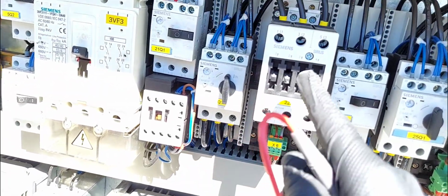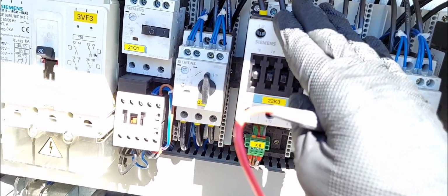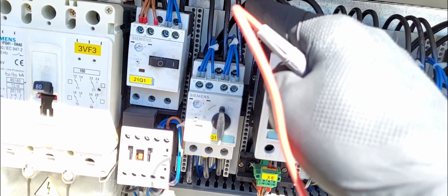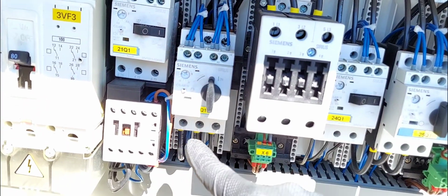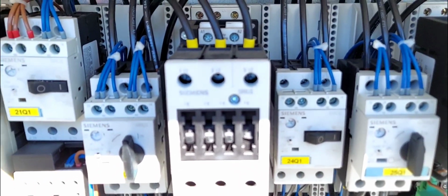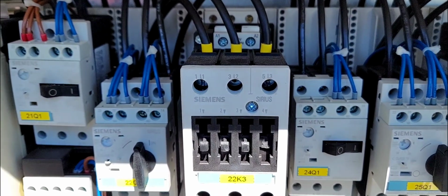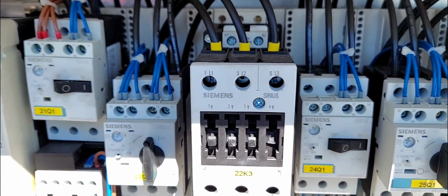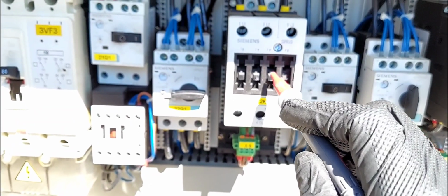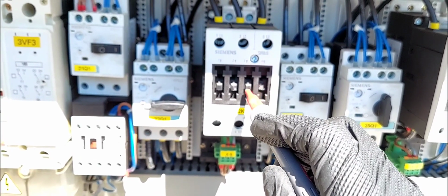So I'm going to turn off the power to the actual compressor which I'm going to be testing. And right here you can see the main power. This is the main power coming in at the bottom here. It comes around to the top of the contactor. It's labeled line 1, line 2, line 3. If I test right here now, I'll have voltage, but I'm going to turn this off. Boom. So I'm off. Now I can simply push the contactor.